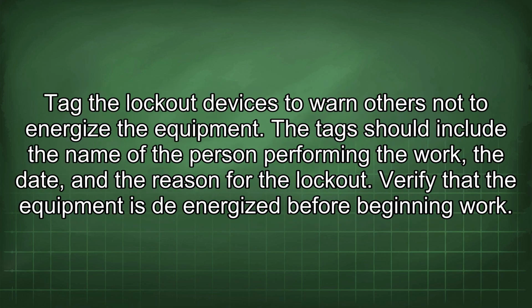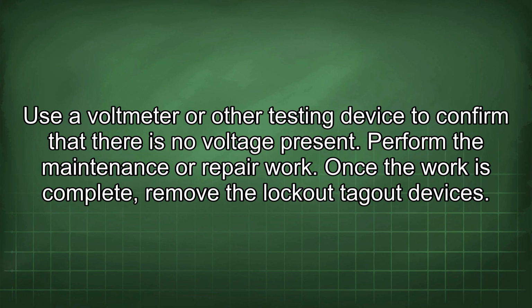Tag the lockout devices to warn others not to energize the equipment. The tag should include the name of the person performing the work, the date, and the reason for the lockout. Verify that the equipment is de-energized before beginning work. Use a voltmeter or other testing device to confirm that there is no voltage present. Perform the maintenance or repair work.